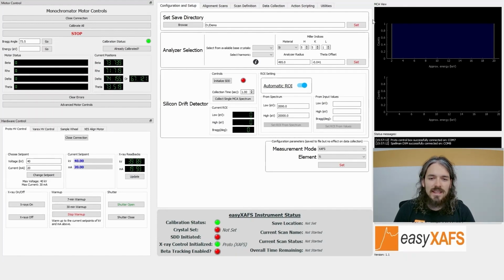Now we'll continue to the configuration and setup in the middle. First we'll set the save directory. Next we'll select the crystal analyzer that we're using for the measurement. Here we're using the silicon 551 crystal analyzer to measure the nickel K edge. The analyzer radius parameter is optimized for this particular crystal and is preset to 495 millimeters. The theta offset is a calibration parameter for alignment of the beam. This is determined by a 1-minute alignment scan, and for the demo, we've already done that, so that's the value we have here.